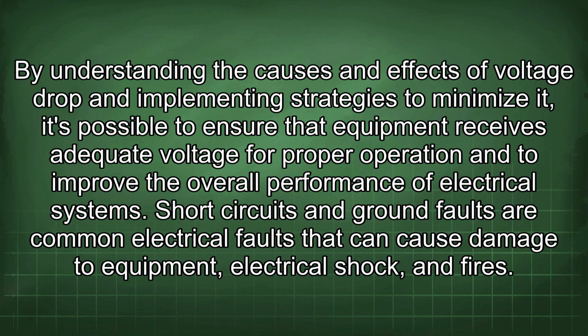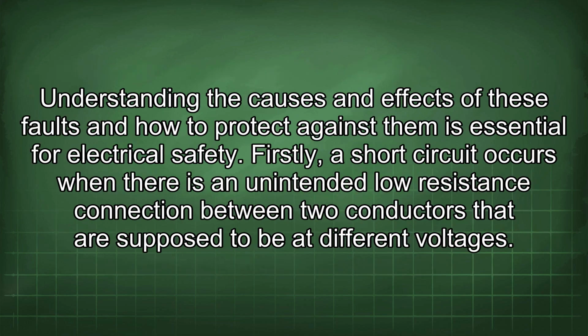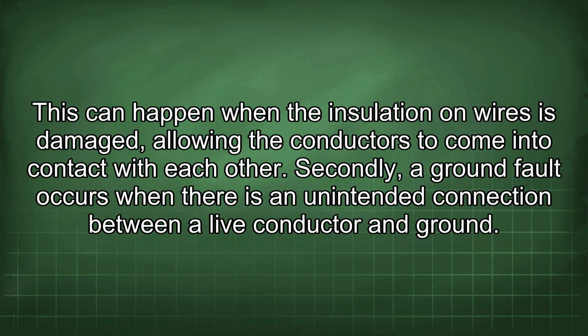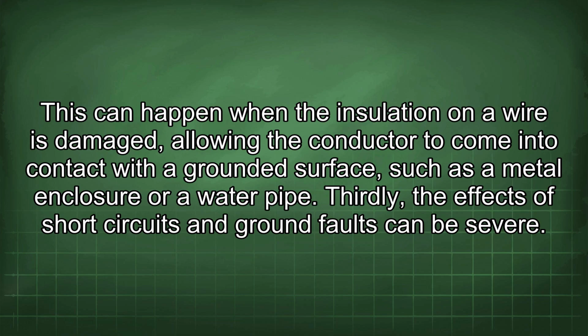Short circuits and ground faults are common electrical faults that can cause damage to equipment, electrical shock, and fires. Understanding the causes and effects of these faults and how to protect against them is essential for electrical safety. Firstly, a short circuit occurs when there is an unintended low resistance connection between two conductors that are supposed to be at different voltages. This can happen when the insulation on wires is damaged, allowing the conductors to come into contact with each other. Secondly, a ground fault occurs when there is an unintended connection between a live conductor and ground. This can happen when the insulation on a wire is damaged, allowing the conductor to come into contact with the grounded surface, such as a metal enclosure or a water pipe.